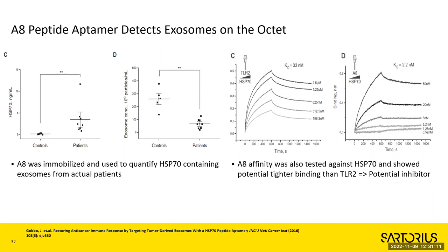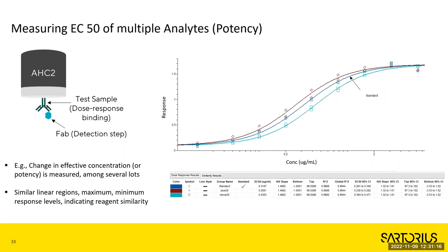An interesting software update is our EC50 and IC50 feature. If you're familiar with S-curves, relative potency, and things like that - EC50 is the concentration producing 50% of the maximum signal generated. When comparing EC50 values, a smaller EC50 means a more potent molecule; if the EC50 shifts higher to the right, it's a less potent molecule. Previously I would take my Octet data, run SoftMax, and figure out how to import and export everything. Now you can do it all within the Octet software.